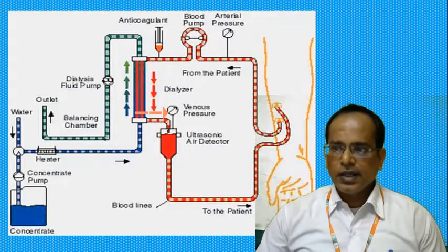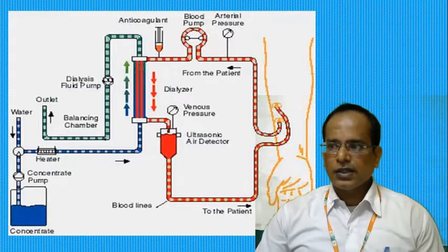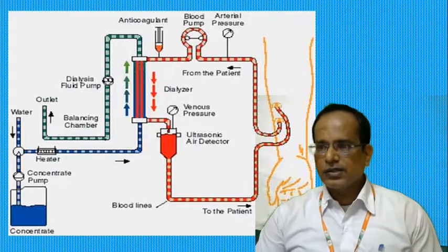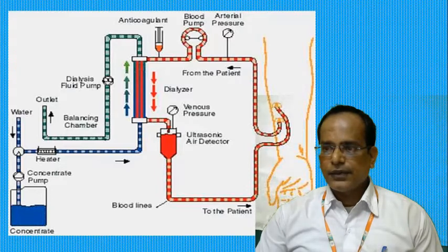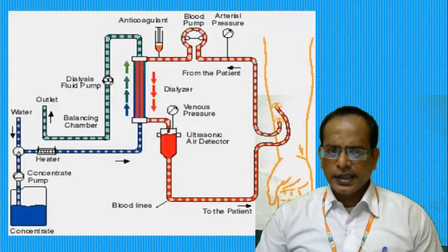So here the concentration of the constituents is adjusted to cause osmotic pressure to force unwanted substances from the blood line into the 8-liter path, and the fluid in this path is recirculated several times and then replaced by fluid from a 120-liter reservoir that you are seeing in the picture.